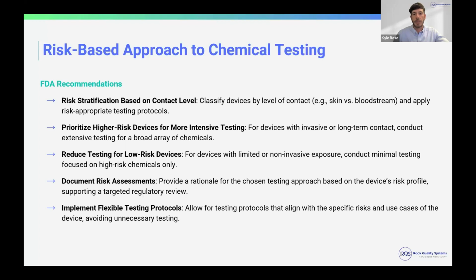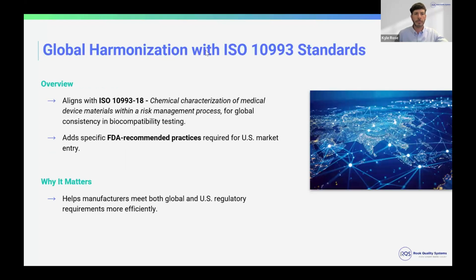Documenting risk assessments within the scope of your QMS, but also potentially within the scope of your submission, to show this risk-based approach. This also can apply for IDE submission. So if you're doing an investigational device exemption for a clinical trial, you might have to include some of this risk assessment as well. And then implementing flexible testing protocols to align with the risks and use cases to avoid unnecessary testing with your product.